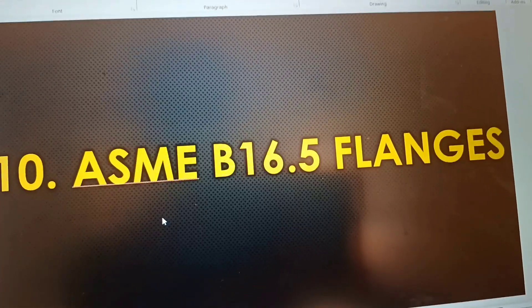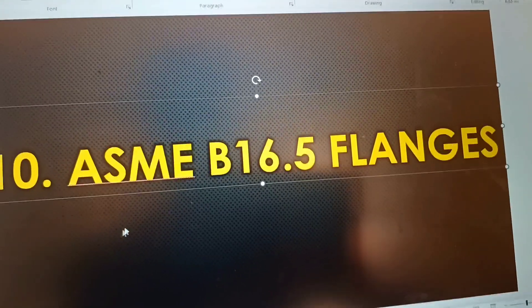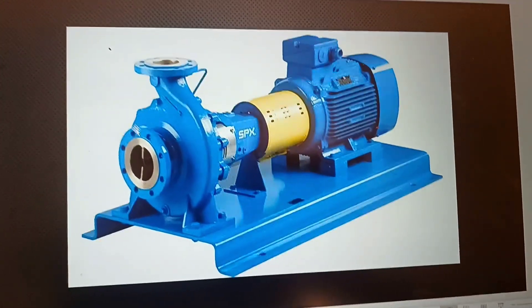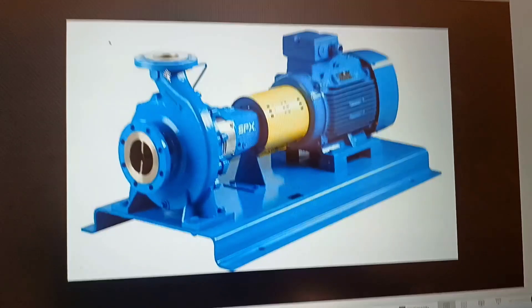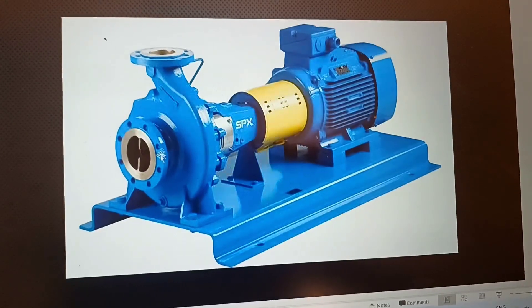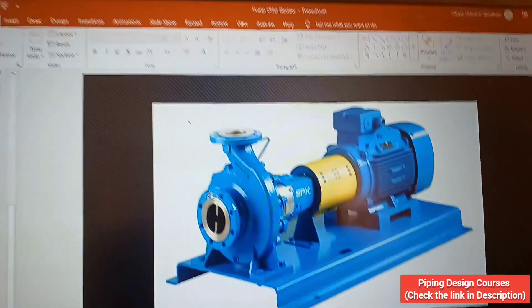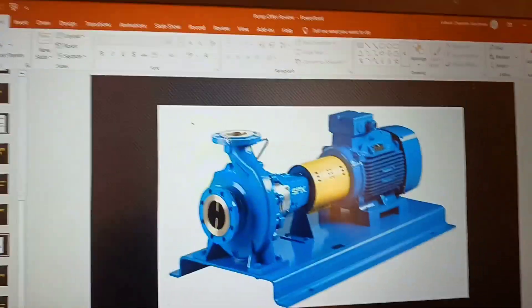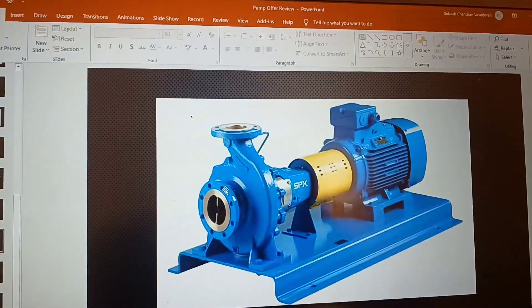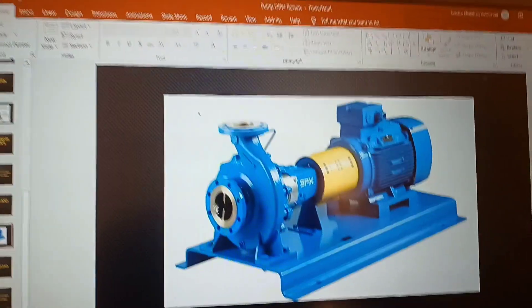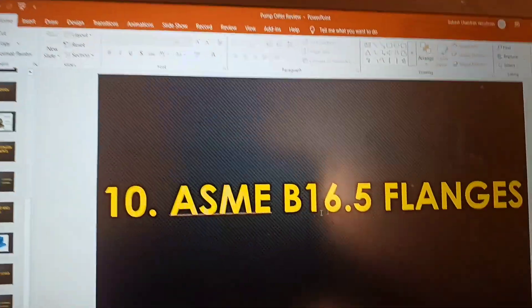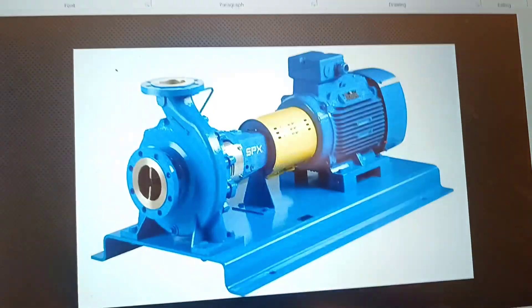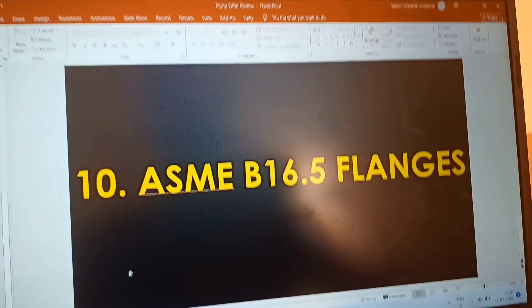The tenth point is ASME B16.5 compliance. All flanges on the suction and discharge must comply with ASME B16.5 because your piping flanges are B16.5-oriented. If the vendor does not comply with this requirement, your piping flanges will not match and you will not be able to connect to the pump's suction or discharge nozzles. You must verify that the sizing, rating, and flange standard all comply with B16.5 in the pump vendor offer.